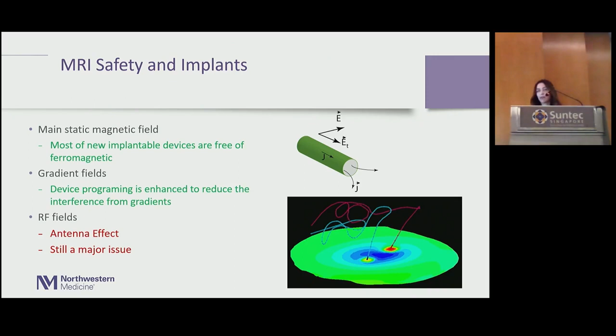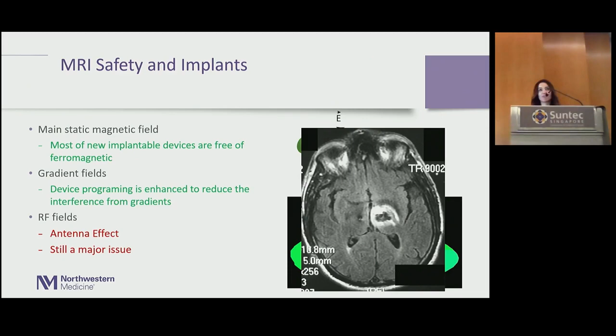So the coupling takes effect, and these electric fields induce currents in the internal wires of these leads. And these currents go back and forth. They can't do anything because these leads are mostly insulated, so they don't go to the tissue along the length of the lead. The tip of the lead is usually what is exposed to the tissue, because that's the part that has to deliver the therapy. So these currents go out to the tissue, which has a low conductivity. Basically, it's more resistive, and they produce a huge amount of local heating. Bad things could happen. We have already done really bad stuff. In 2005, a patient with a deep brain stimulation implant underwent MRI at 1 Tesla, and basically had a huge burn due to local heating and didn't survive.